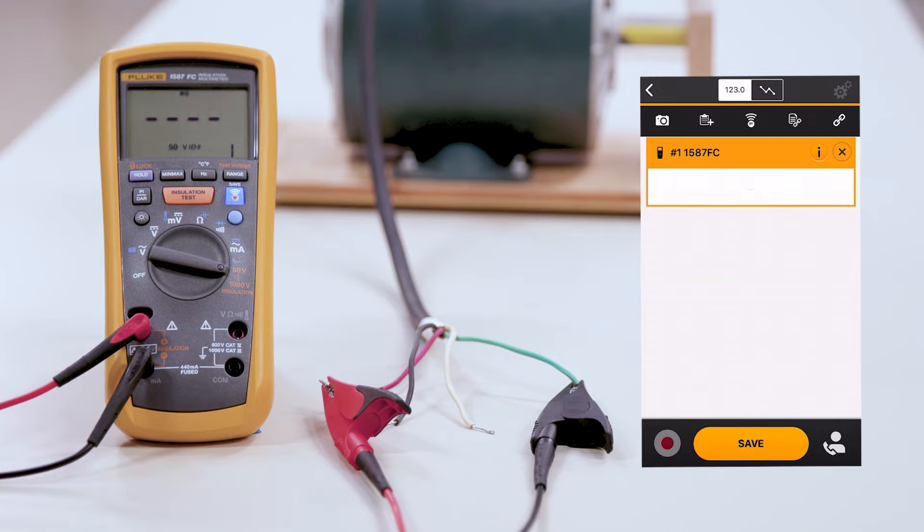Typically, in an insulation test, we want to double the value of whatever the rating is for voltage. In this case, this motor is a 480 volt motor. We're going to change the range of our insulation meter to 1000 volts.